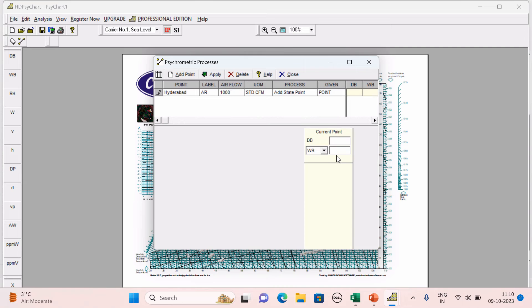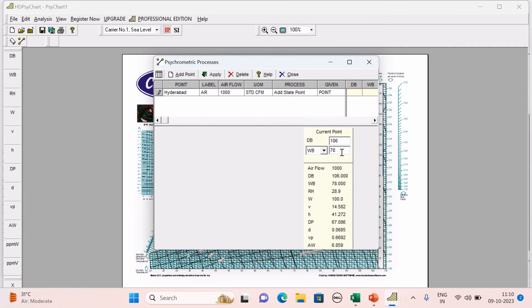Outside dry bulb temperature for Hyderabad is 106°F, and wet bulb temperature is 78°F. Enter these two properties in the software. The humidity ratio shown is 100 grains per pound — this is the outside specific humidity or humidity ratio for Hyderabad.